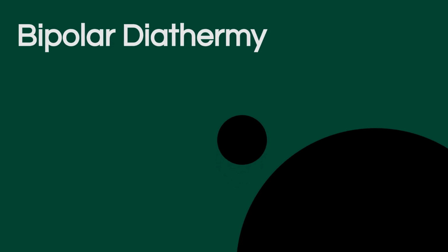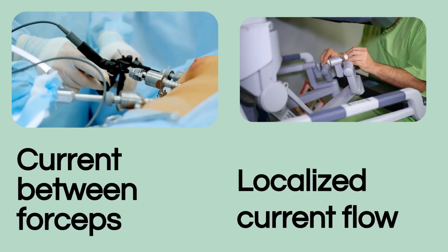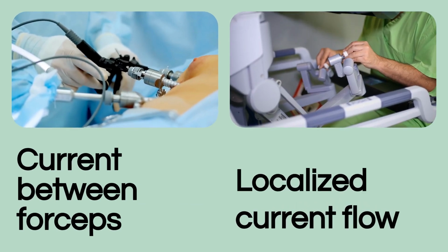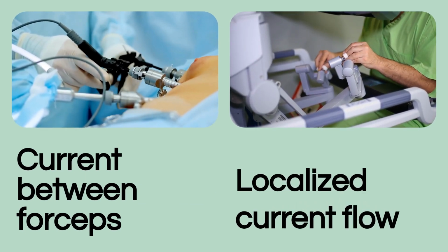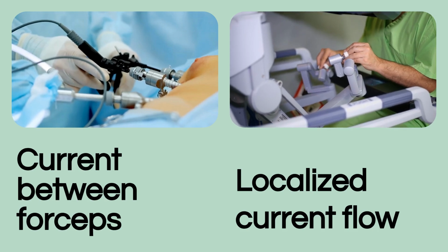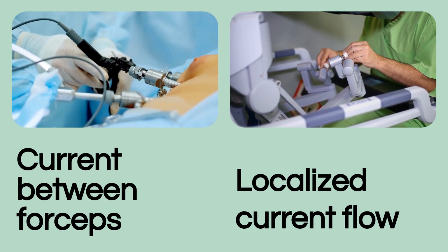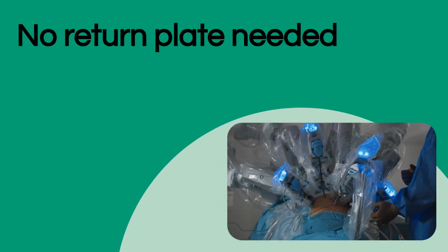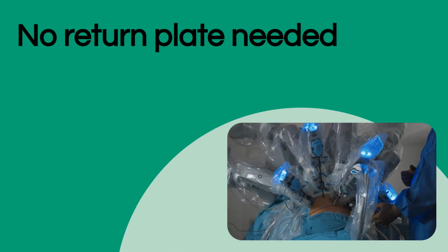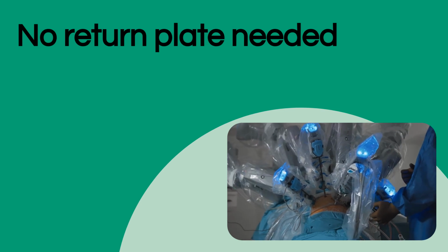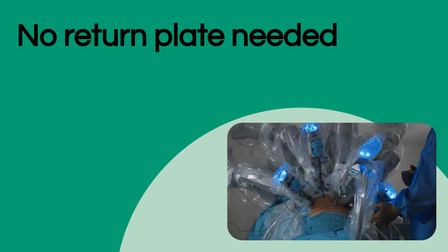Next, we have bipolar diathermy, which operates on a different principle. In bipolar diathermy, the active probe resembles forceps. The current flows down one tip, through the tissue, and immediately returns up the other tip, strictly localizing the current path. A key advantage here is that no return plate is required, as the current does not travel through the patient's body. This makes it ideal for delicate surgeries, needing precise coagulation.